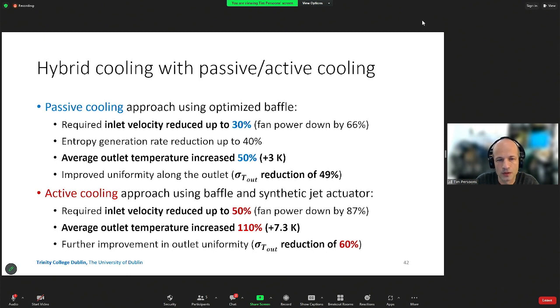That means that we can increase the outlet temperature, and we are also improving the uniformity of the outlet temperature, which is also useful for waste heat recovery. The added benefit of having the synthetic jet actuator is that you can further improve these numbers, but you also have more adaptive control possibility, of course, because if the server goes from 100% utilization to a lower utilization, all of those thermal loads will change. And if you have some local components, for instance that synthetic jet actuator that you can either enable or disable, or you can modulate the cooling performance somewhat, then it gives you more flexibility to trim out those differences and those modulations.